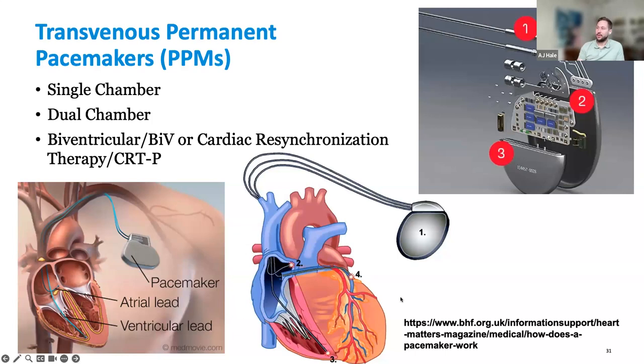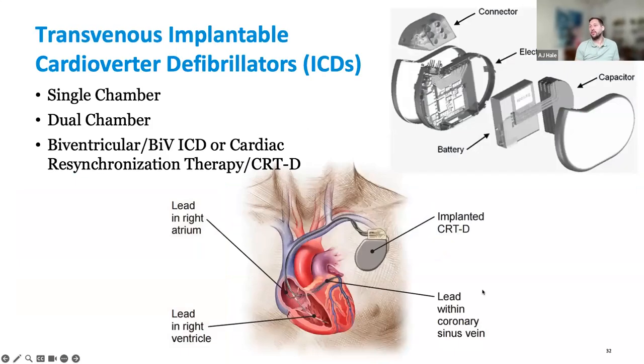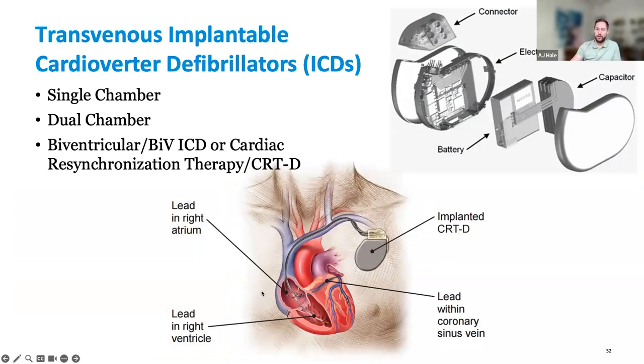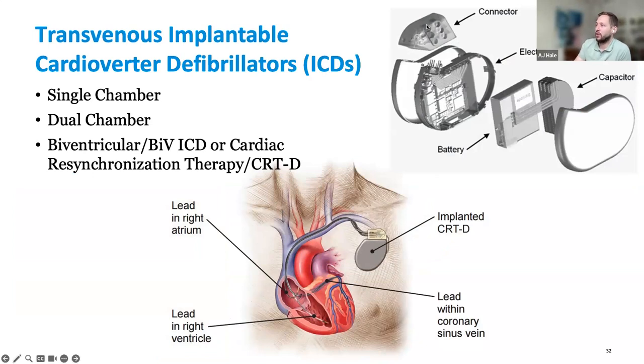Moving along, we have ICDs. ICDs are very similar in structure to a pacemaker, aside from the ability to defibrillate. Like a pacemaker, you have your header, circuit board, and battery. The key difference structurally, aside from a more complex circuit, is the capacitor, which allows it to deliver a massive charge. Batteries are like a tank with limited energy output; the capacitor takes a large amount of energy, stores it, and then releases it to defibrillate the heart.